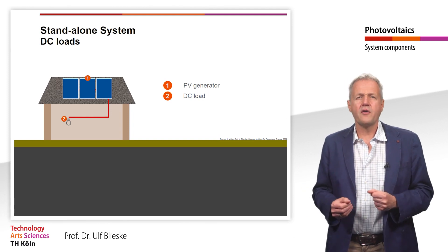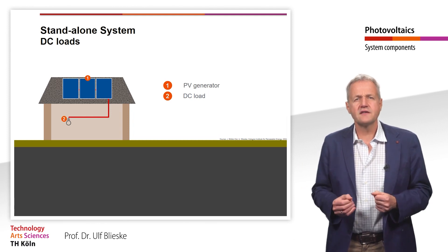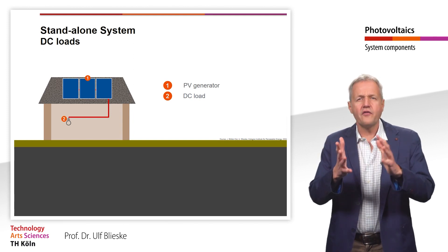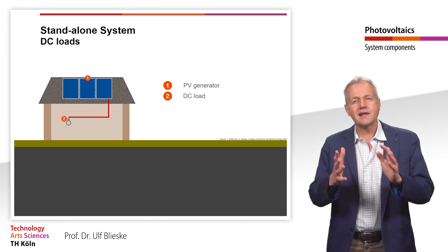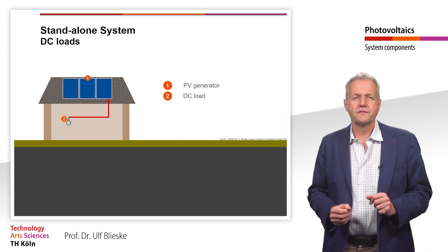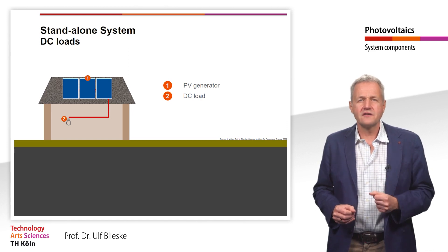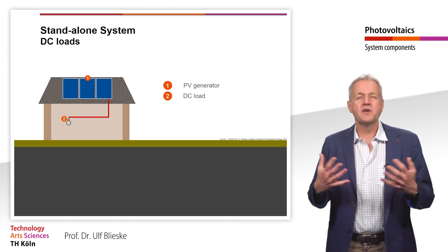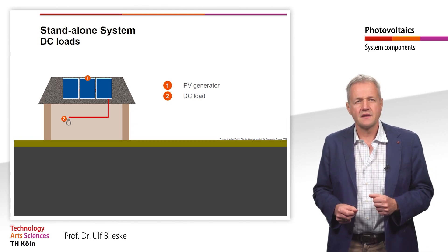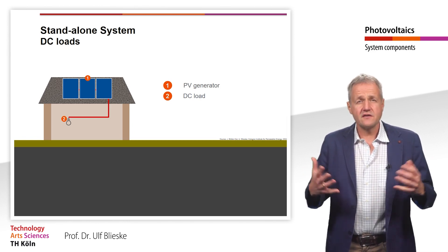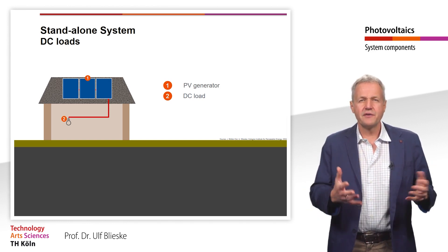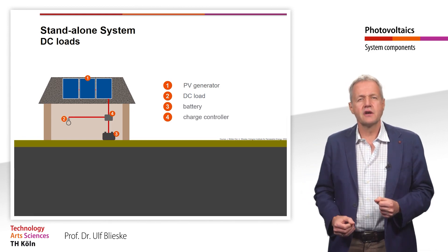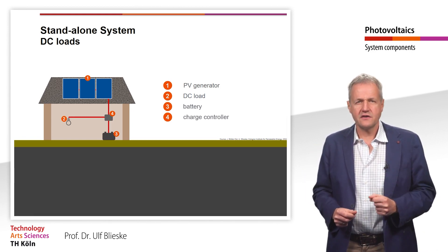The simplest form of such a standalone PV system is a directly coupled system, where the DC output of a PV module or array is directly connected to a DC load. However, the load in this system can only operate when the sun is shining and the PV modules are generating power. If it is also to be operated at night or during periods of low irradiation, a battery storage must also be integrated into the system.